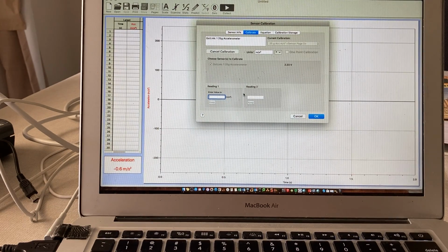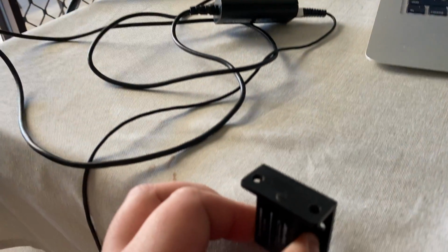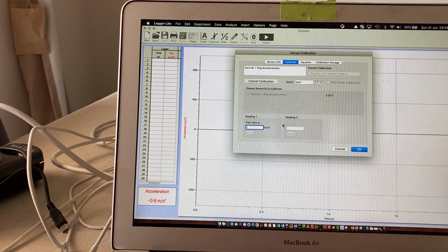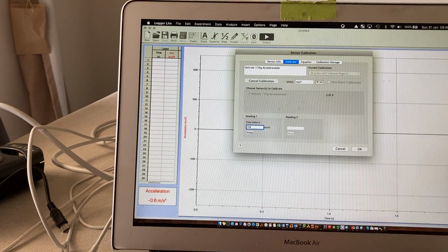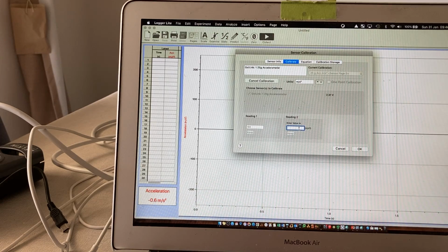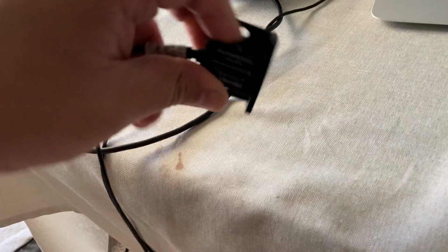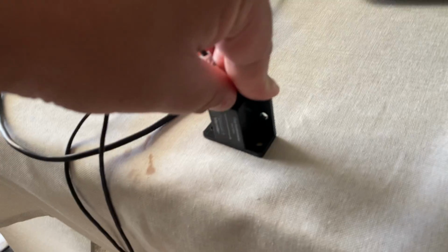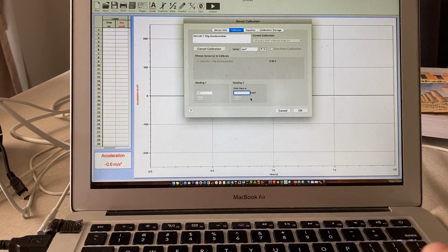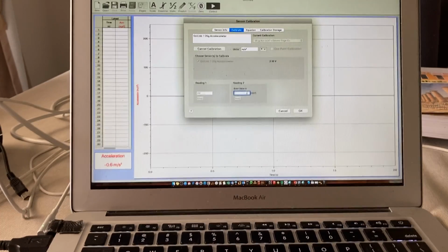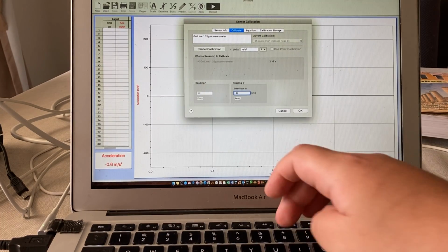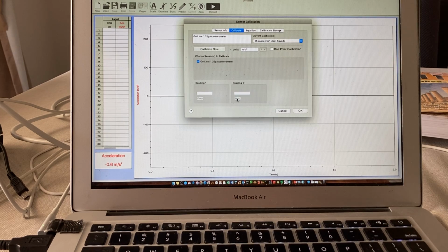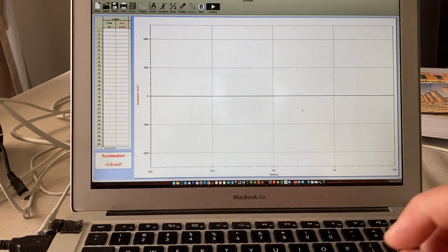So the first reading that you're going to do, reading 1, I'm going to hold the accelerometer pointing directly up. I'm using the table edge to help me. So that's pointing vertically. And that should be an acceleration of 9.8, not negative 9.8, 9.8 because it's pointing up. And I'm going to press Keep. And now I'm going to turn the accelerometer pointing straight down. Ignore the chocolate stains there. It's pointing directly down, and we know that gravity at the surface of the Earth is negative 9.8 meters per second squared. So I'm going to hit that, Keep it, press OK.